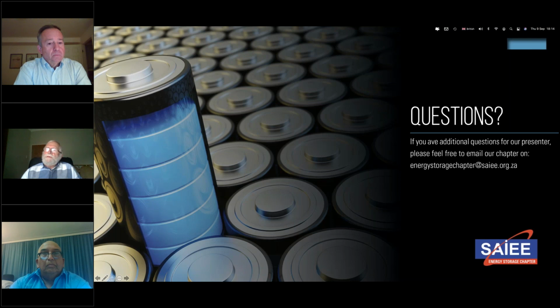I think that's in response to the round trip efficiency. The round trip efficiency is a factor if the electricity you're charging with is expensive. For example, if electricity from a large solar field is inexpensive, maybe 3 cents a kWh, and you're losing 30% going through a battery, you're talking about a penny of cost, versus grid electricity at 10 cents kWh, where you're talking about 3 cents. So the economic impact of round trip efficiency matters if you're using expensive grid electricity to charge the battery. It doesn't have much impact on a project pro forma if you're using very inexpensive wind or solar energy to charge it.